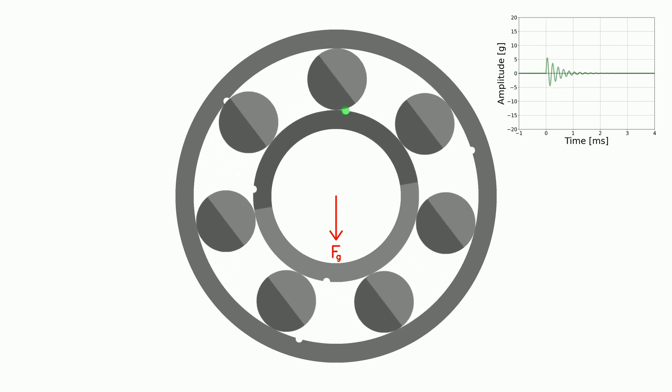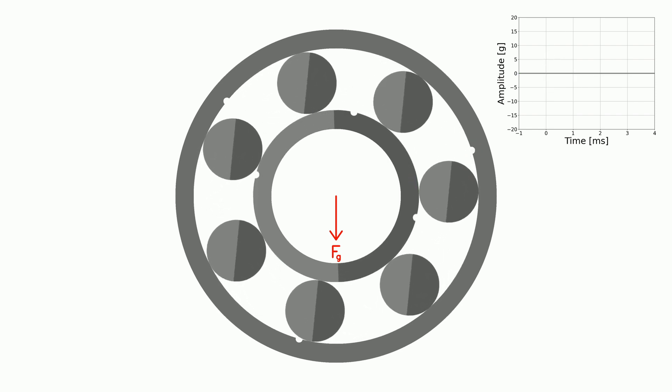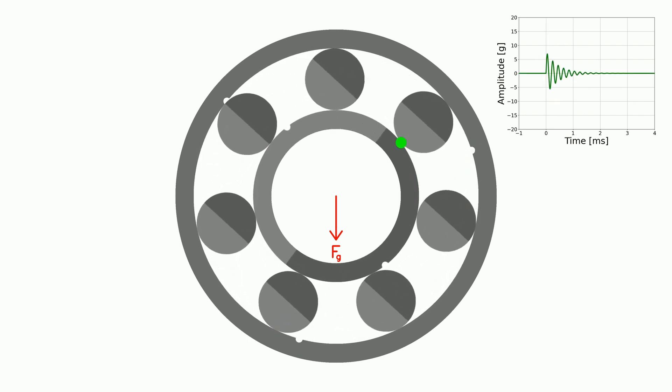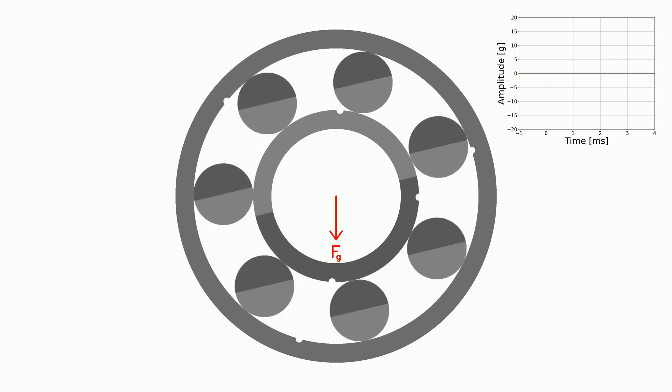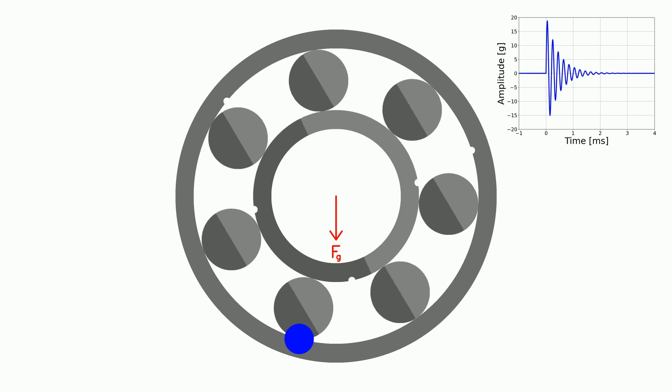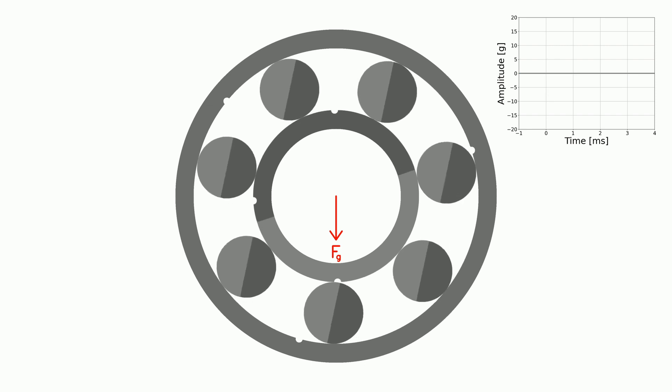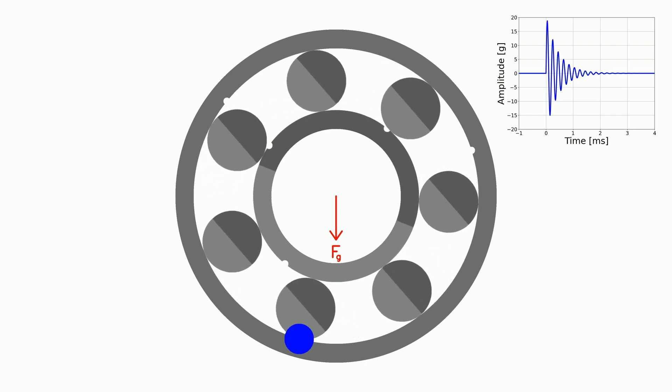This is true for both races. In this case, only inner race shocks are modulated. The outer race shocks are not modulated. It is because the position of each outer race fault relative to Fg is constant.